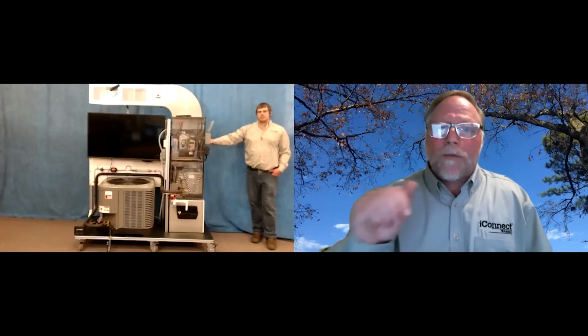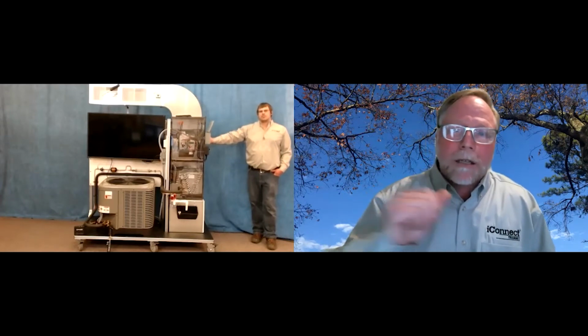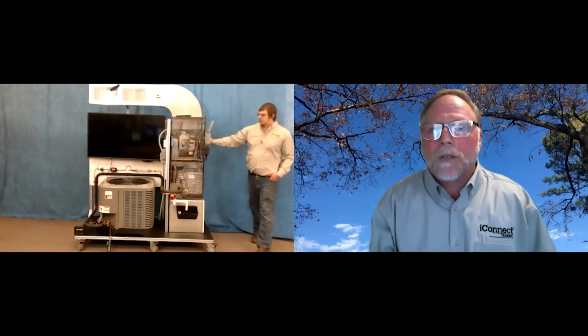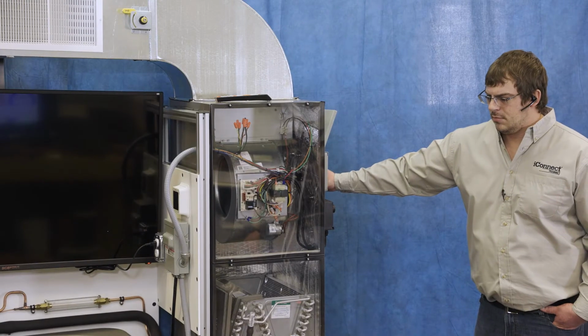The only thing that's helping us out here is we got an expansion valve, and you can see how that expansion valve is trying to maintain that superheat like it's supposed to do. But look at there, the head pressure keeps going up and up. Now, Nick, if you would, go ahead and flip the fan switch back on, and let's get the condenser fan back in operation, and let's watch it and see what happens to it.